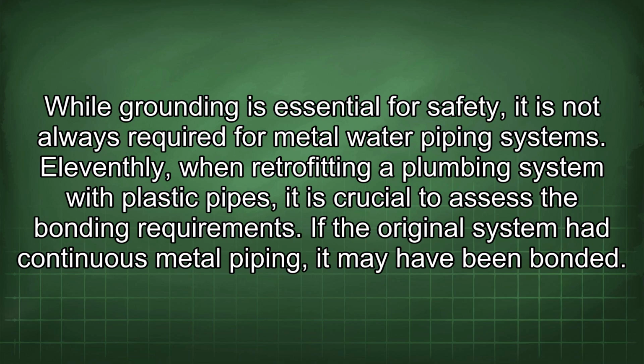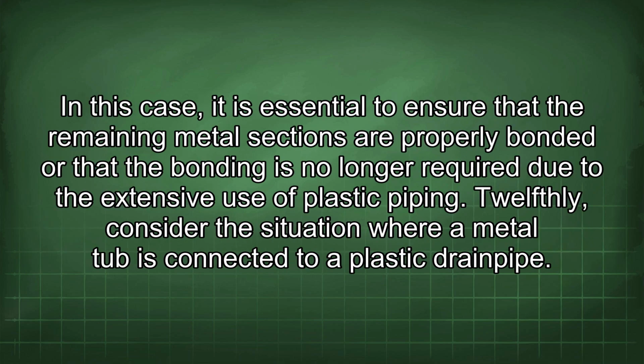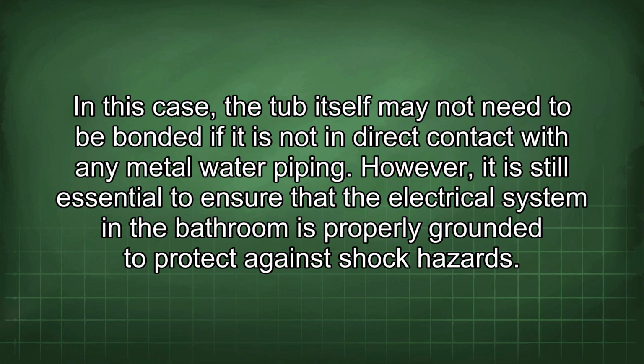Eleventhly, when retrofitting a plumbing system with plastic pipes, it is crucial to assess the bonding requirements. If the original system had continuous metal piping, it may have been bonded. In this case, it is essential to ensure that the remaining metal sections are properly bonded or that the bonding is no longer required due to the extensive use of plastic piping. Twelfthly, consider the situation where a metal tub is connected to a plastic drain pipe. In this case, the tub itself may not need to be bonded if it is not in direct contact with any metal water piping. However, it is still essential to ensure that the electrical system in the bathroom is properly grounded to protect against shock hazards.